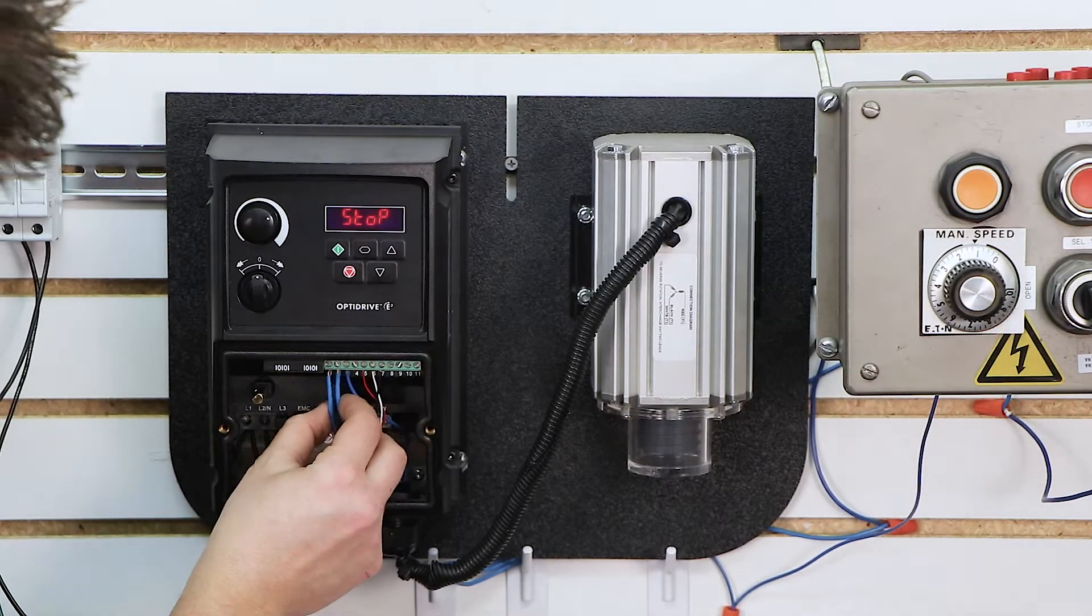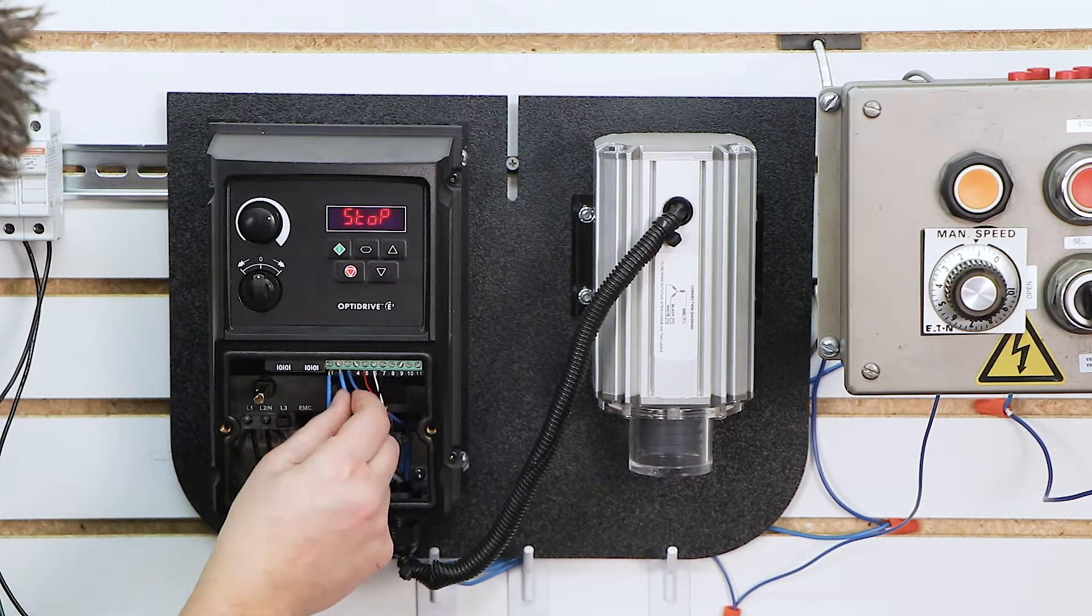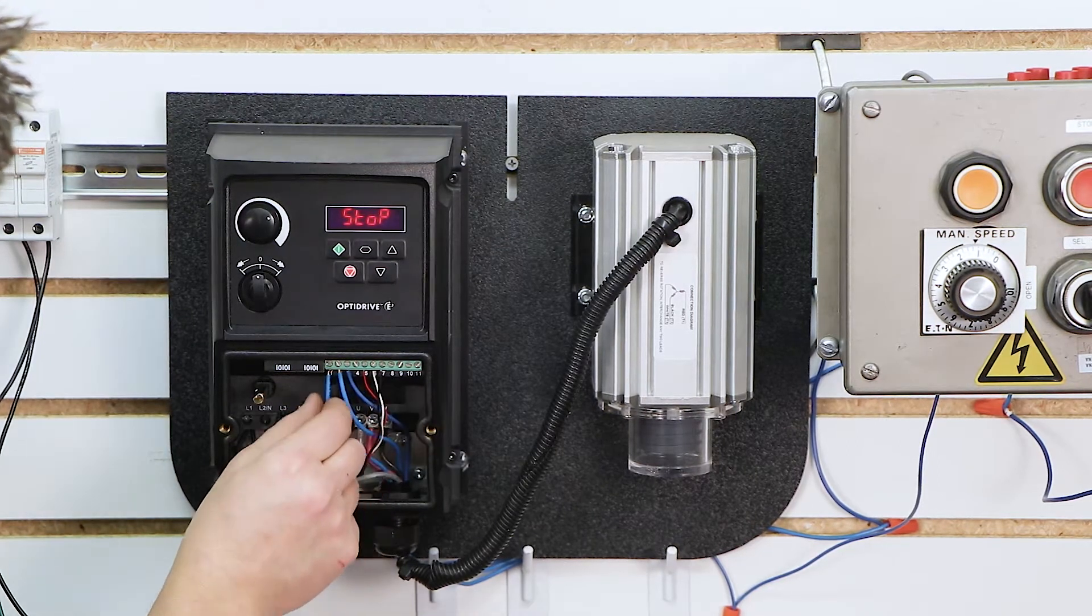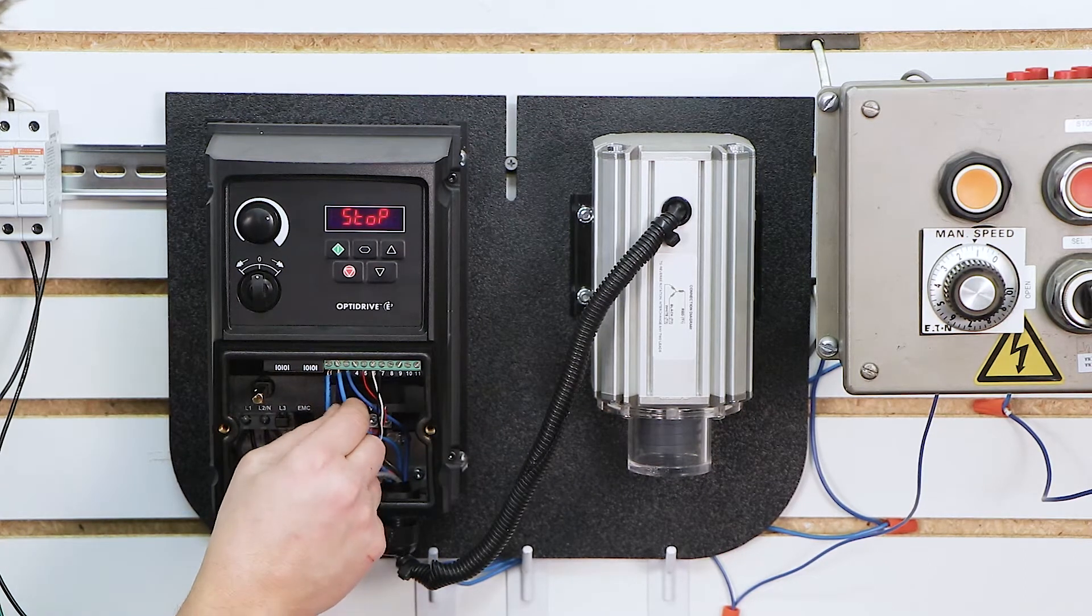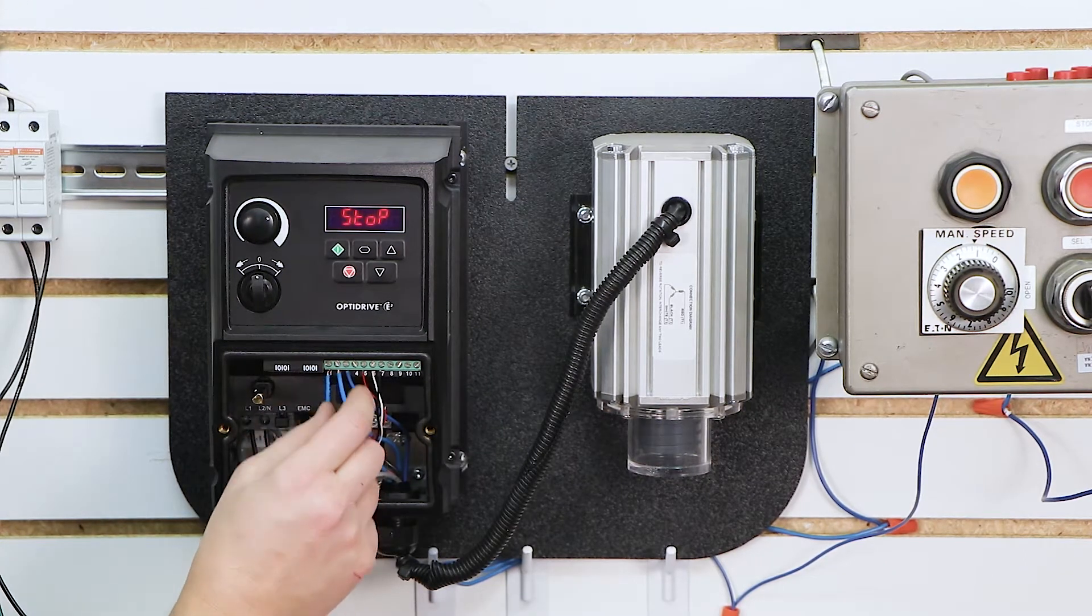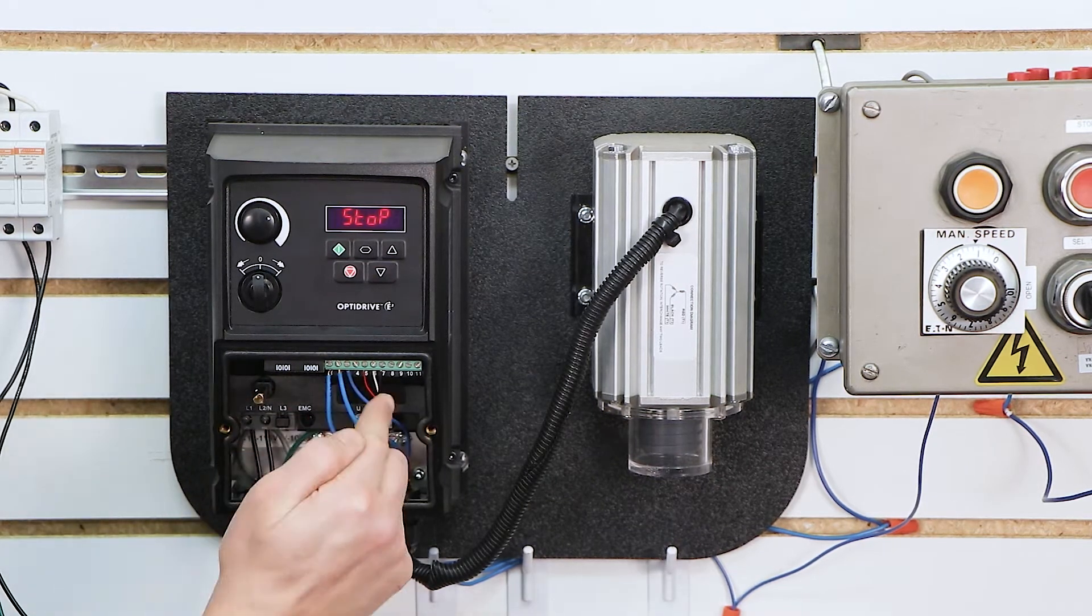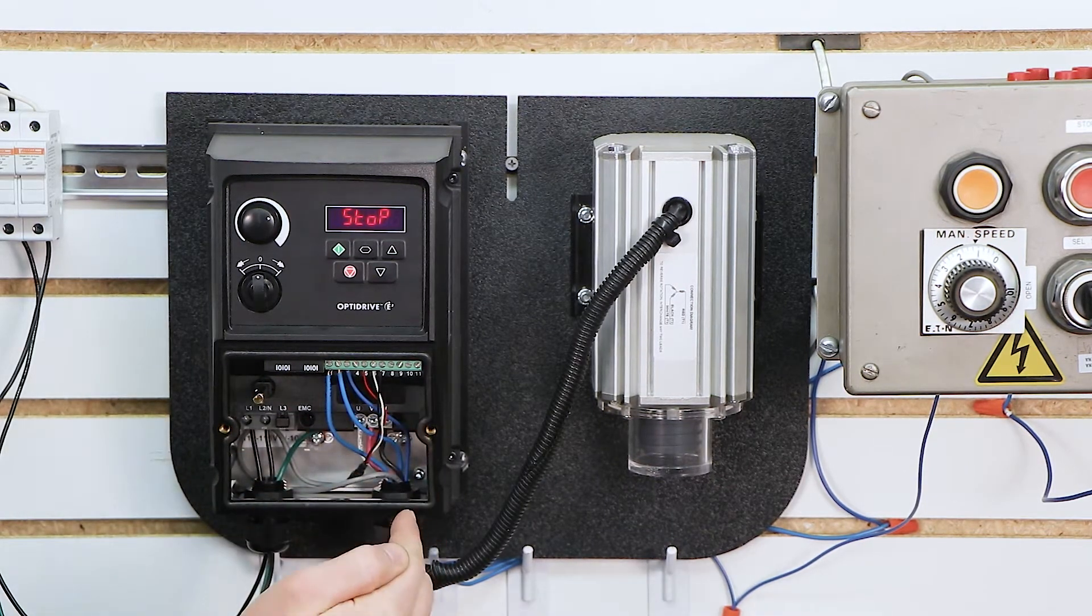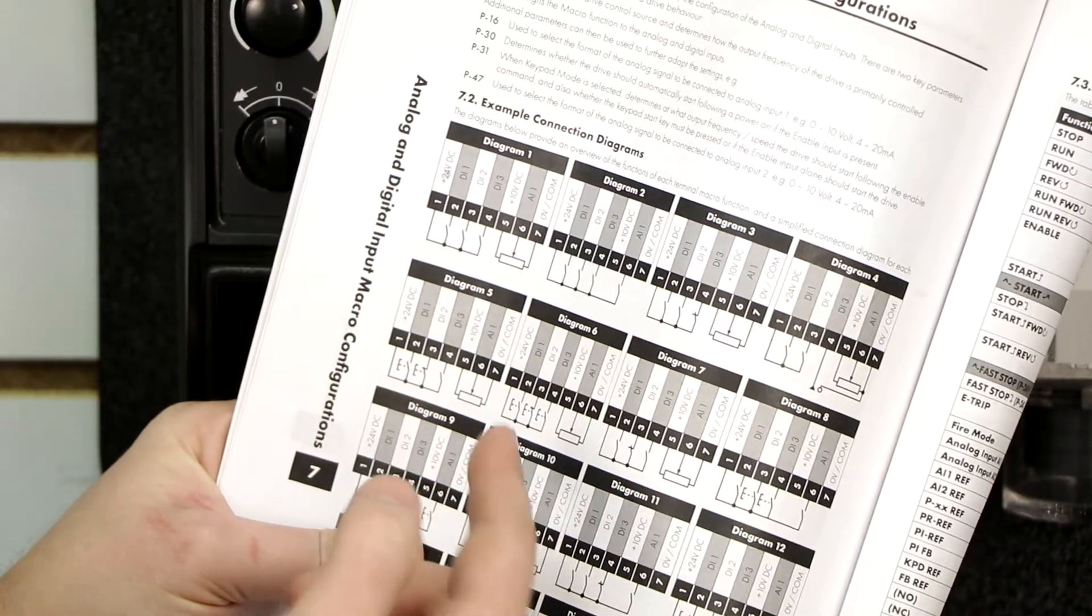So what I did is I've got my digital input 2 going into one side of my push button, digital input 1, which is plus 24 volts, going into the other side of my start push button, and then the contacts on the back of that start push button are normally open. That means that voltage doesn't flow until I press the button down.